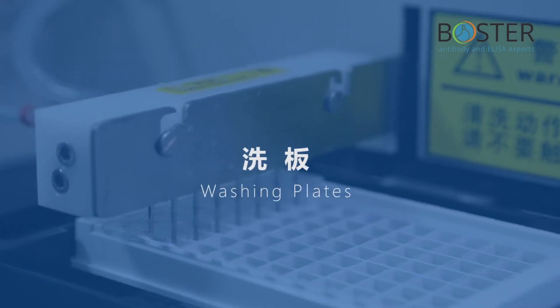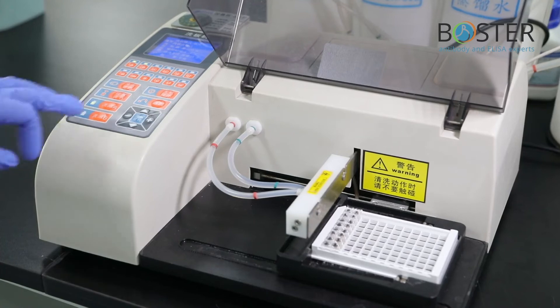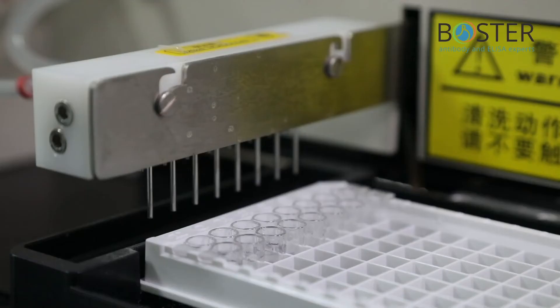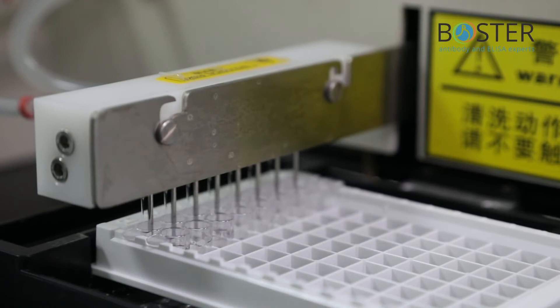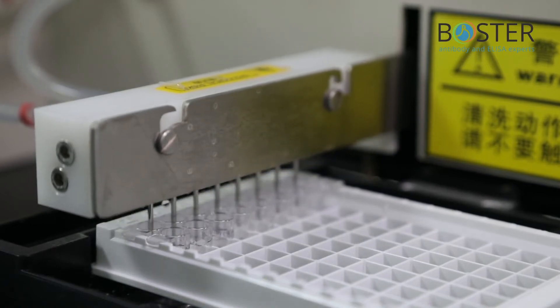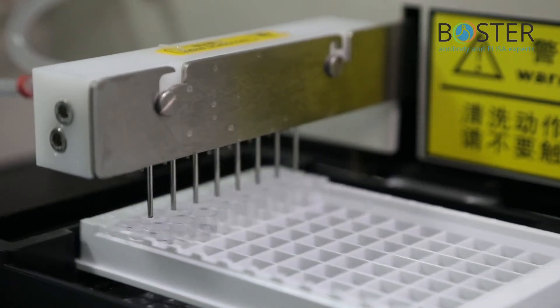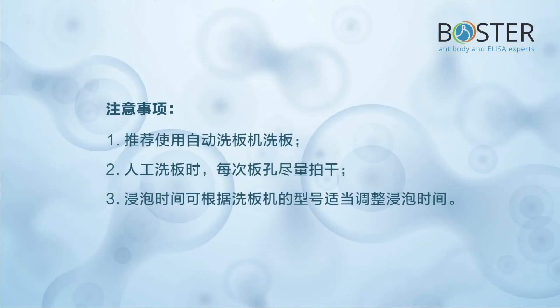Step 3: Wash the plate. After the reaction, wash three times with 1X washing solution. Add 300 µL of washing buffer to each well and soak for one minute each time. Precautions: 1. It is recommended to use an automatic plate washer to wash the plate. 2. When washing the plate manually, try to pat the plate as dry as possible. 3. Adjust the soaking time according to the model of the plate washer.